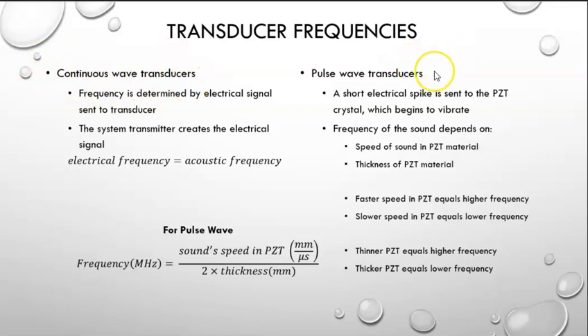For imaging transducers or pulse wave transducers, a very short single electrical spike is sent to the PZT crystal, which causes it to vibrate. The vibration will occur at a specific frequency based on the PZT material itself. And that frequency is due to the speed of sound in that material, the stiffness of the material, and the thickness of the material. So that's why we had that 1/2 crystal thickness: the thickness of the PZT material was 1/2 of the wavelength in the transducer.